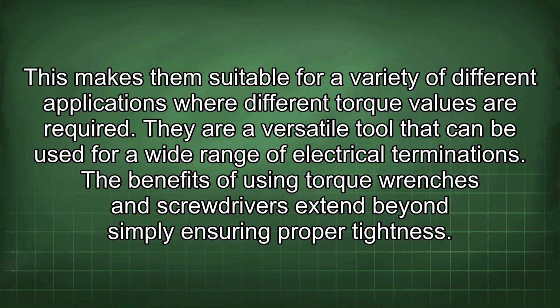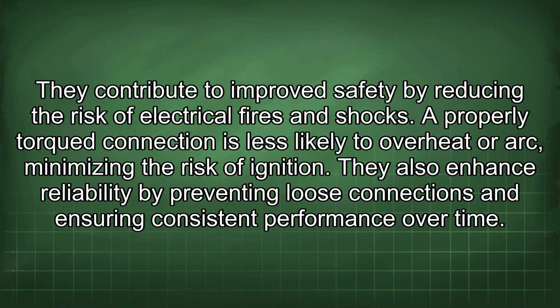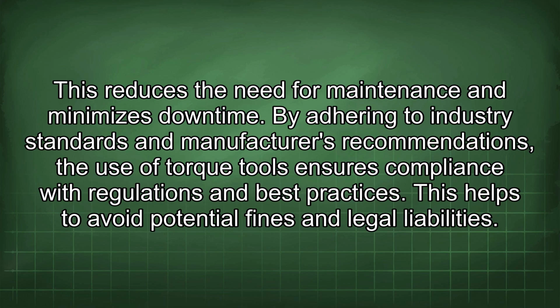The benefits of using torque wrenches and screwdrivers extend beyond simply ensuring proper tightness. They contribute to improved safety by reducing the risk of electrical fires and shocks. A properly torqued connection is less likely to overheat or arc, minimizing the risk of ignition. They also enhance reliability by preventing loose connections and ensuring consistent performance over time, reducing the need for maintenance and minimizing downtime.